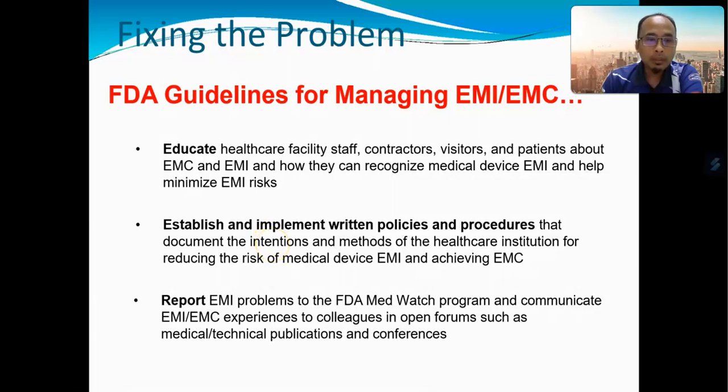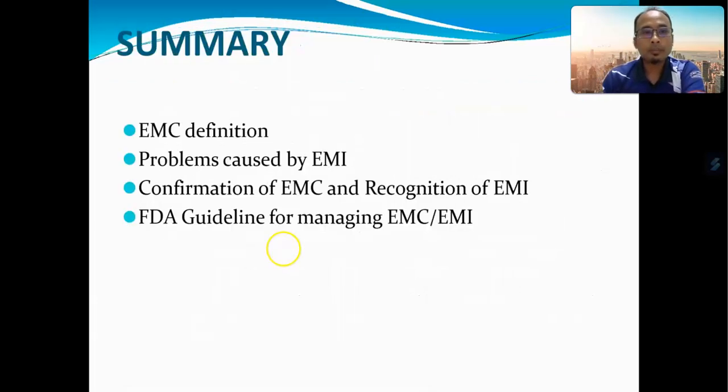And then finally, we can report EMI problems to the FDA MedWatch Program and communicate EMI or EMC experiences to colleagues in open forums such as medical or technical publications and conferences.